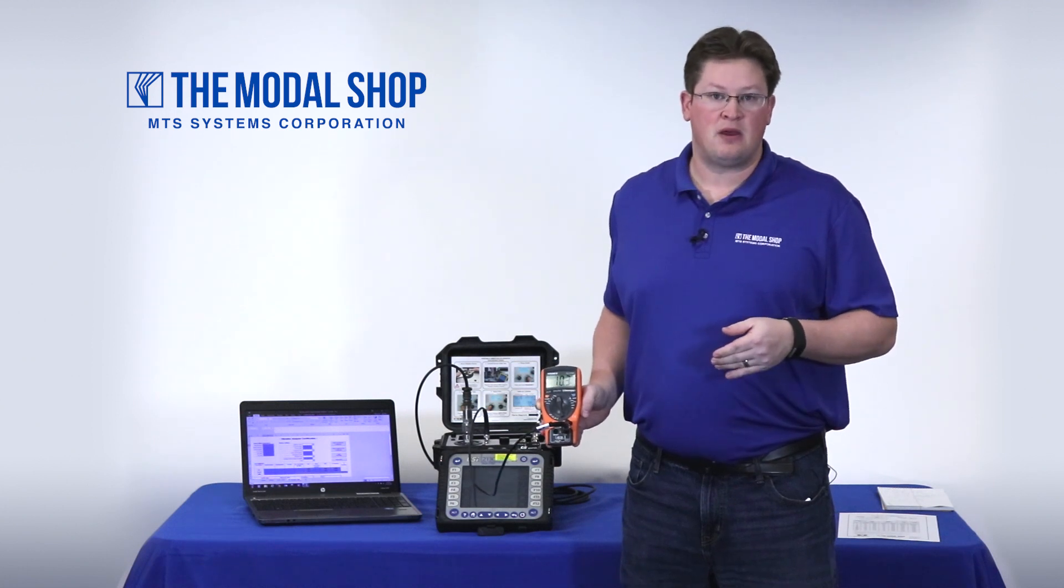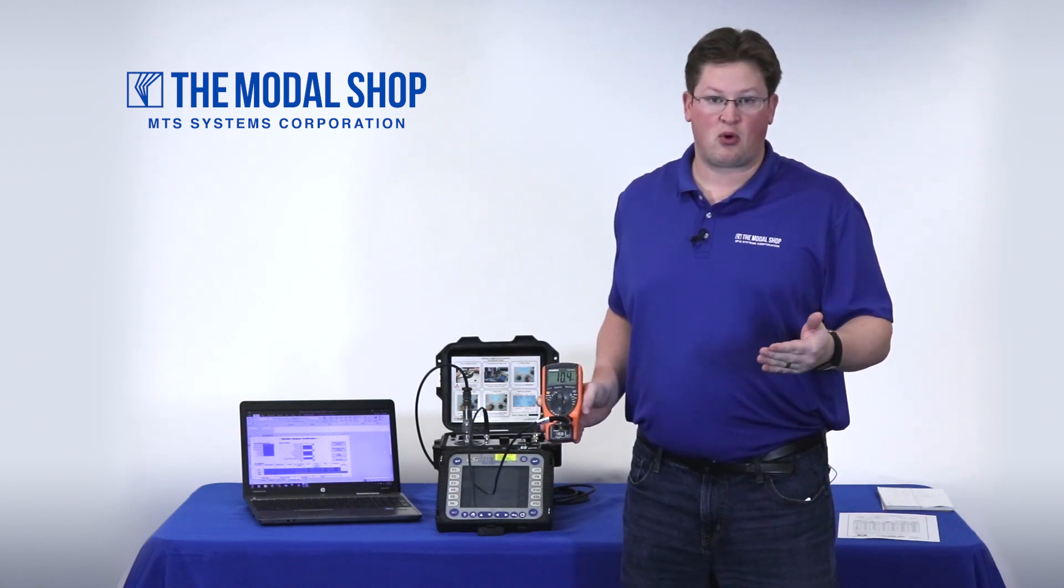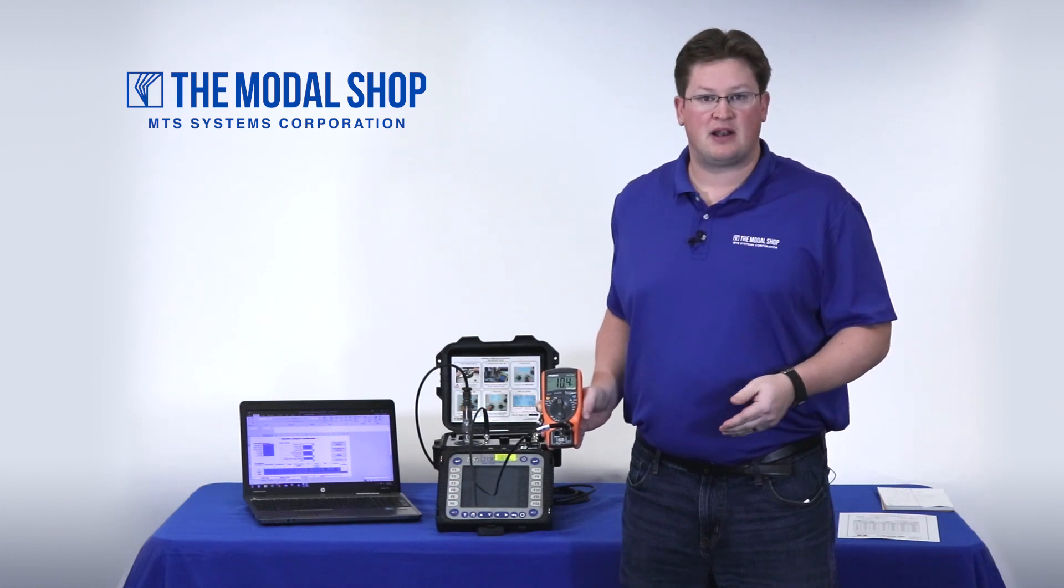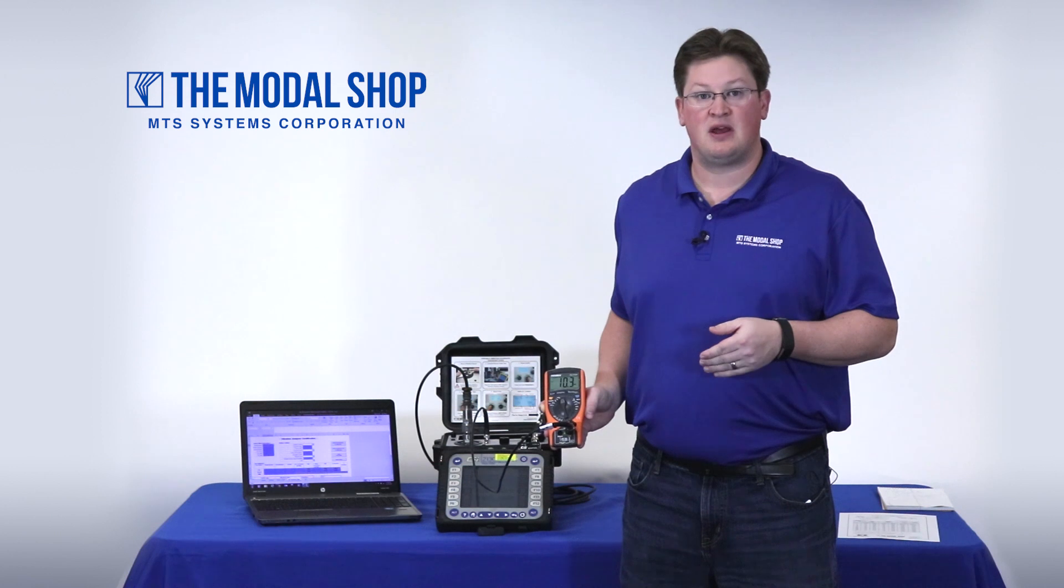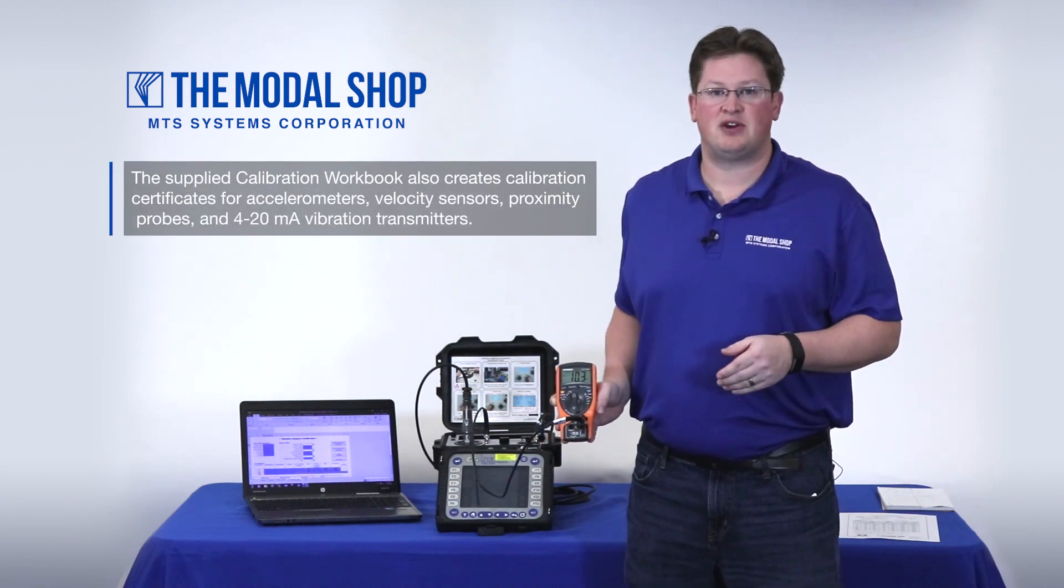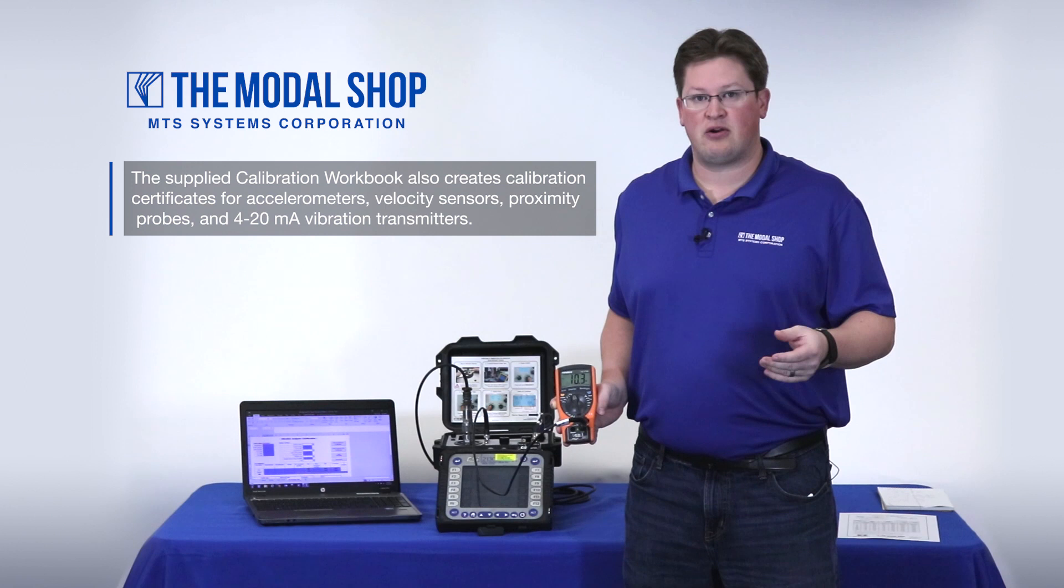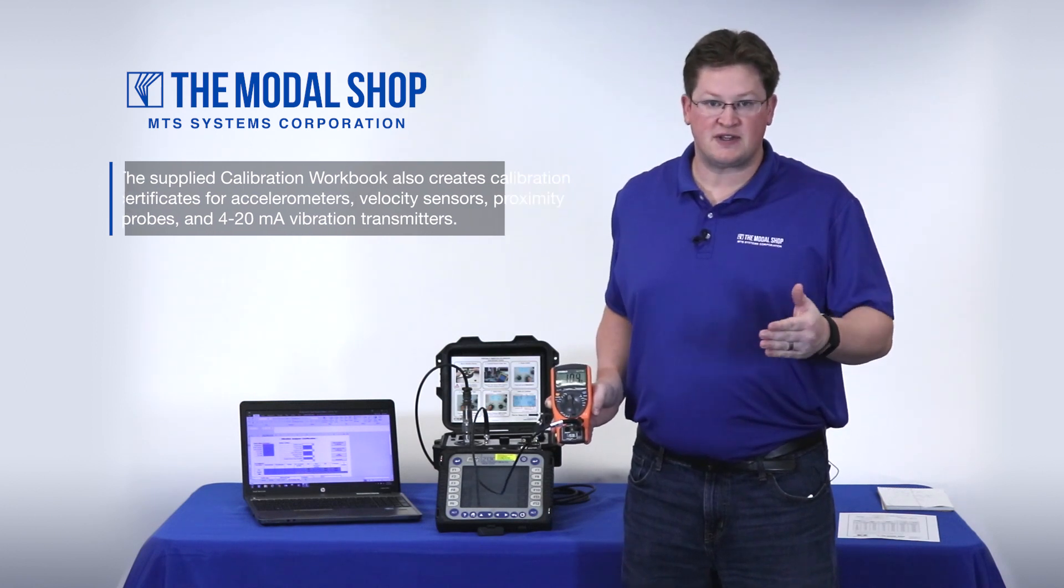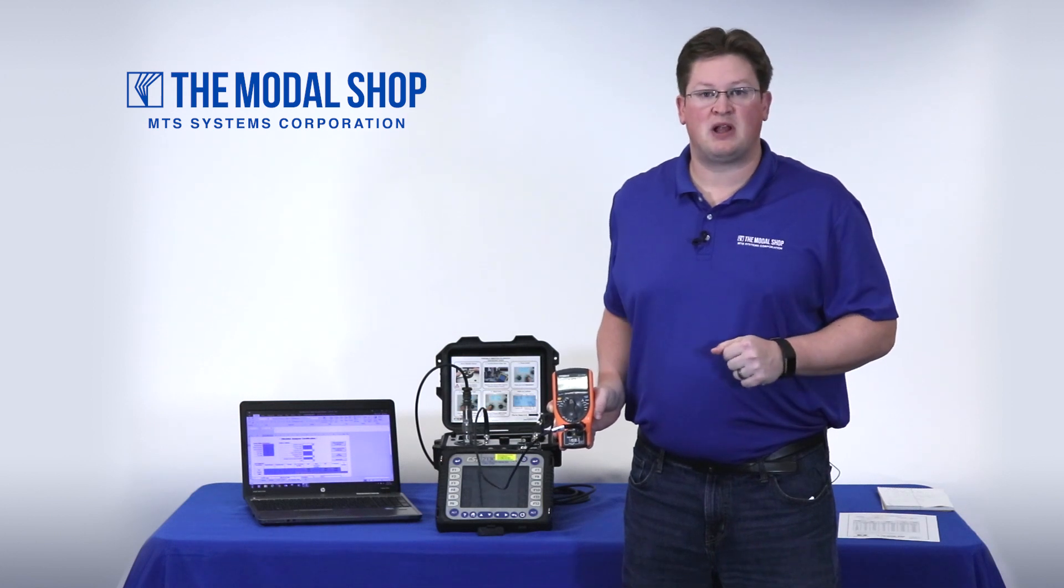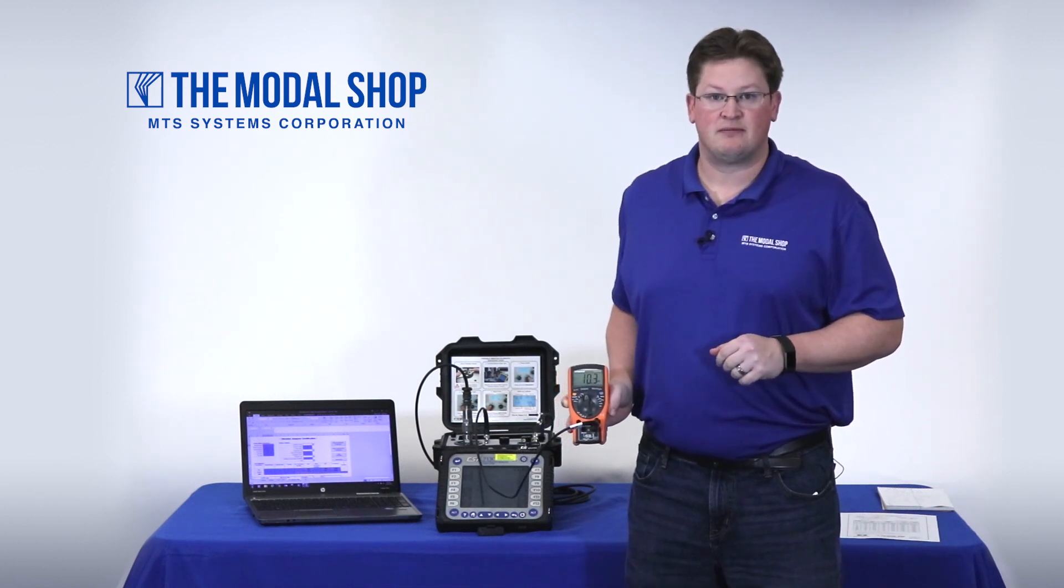Lastly, we've created a new element to our supplied calibration report generation workbook in Microsoft Excel that allows you to key in the values from the Portable Vibration Analyzer to produce a NIST traceable calibration certificate for both linearity and frequency response. The first thing we're going to do in the test is check the accelerometer that's been supplied with our 2130. So let's get started.